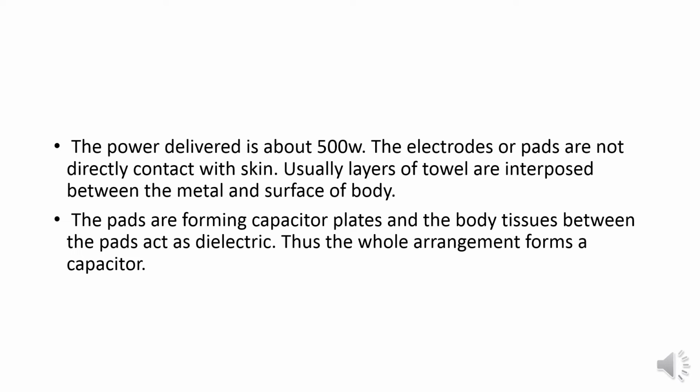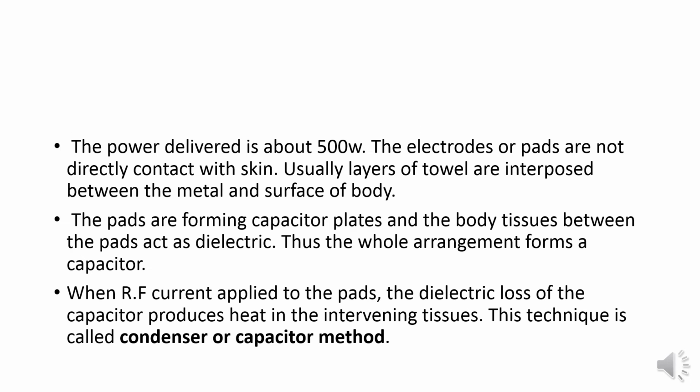Thus the whole arrangement forms a capacitor. When RF current is applied to the electrodes, the dielectric loss of the capacitor produces heat in the intervening tissues. So this technique is called the condenser or capacitor method.